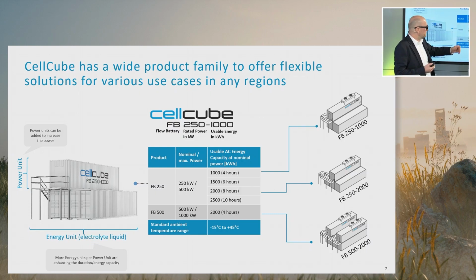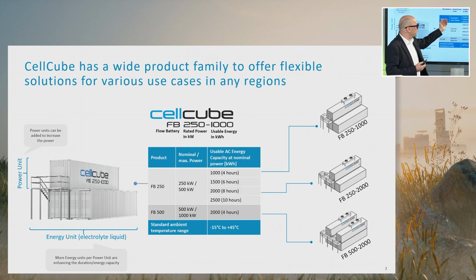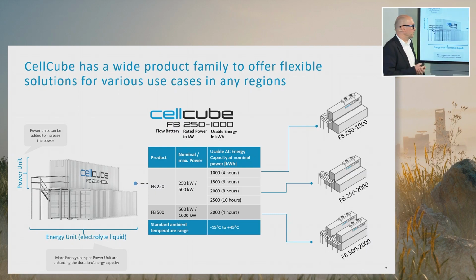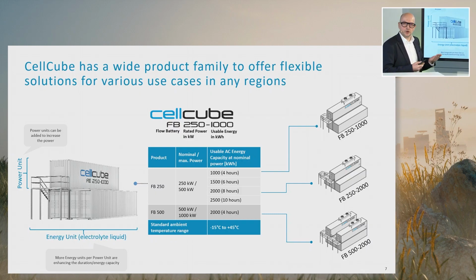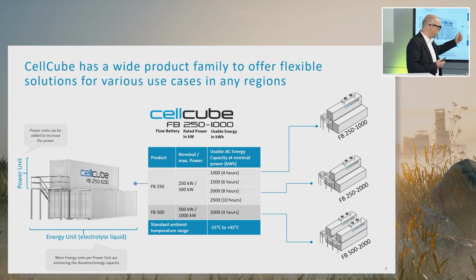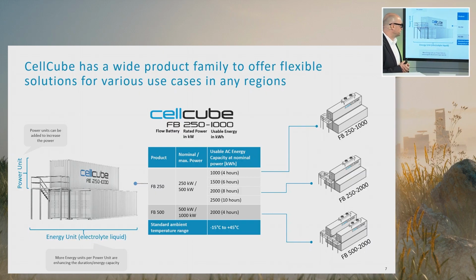With the amount of bottom containers, you can form now your usable AC capacity. So you can have 1,000 kilowatt hours for a 4-hour discharge battery, 1,500 for a 6 hours discharge battery, 2,000 for 8 hours, and 2,500 for 10 hours. This would be our standard products. And if you put 2 power units on the top of the container, you get an FB500, which then, of course, has a max power up to 1 megawatt, and in this case, the 4-hour system.